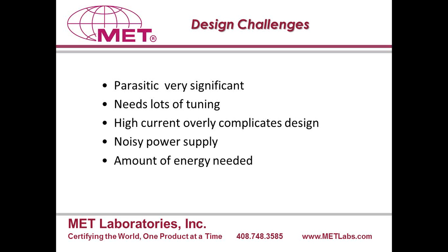Another challenge has been the noisy power supplies. We have been using commercially available power sources for 48 volt DC and 75 volt DC. Especially with the 48 volt DC system, if off-the-shelf power supplies are used as is without any treatment, they cause serious problems. Waveforms are never clean, and it becomes a challenge to get the correct waveform. However, with some special techniques, we managed to overcome this problem, clean up the noise and get the right waveforms.